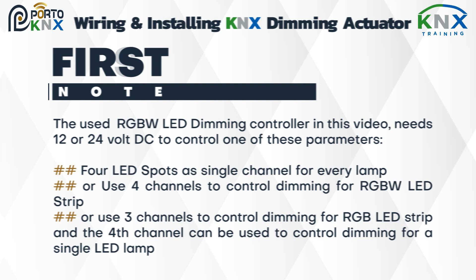Now we also need to use a power supply to convert from 220V AC to 12V DC, because the LED spot used in this video is fed by 12 volt DC. Second note, we will use an MCB to protect all electric circuits and smart devices, so the rated current of this MCB should not exceed the rated current of the actuator output channels. Also, the connected loads should be within the range of this MCB.